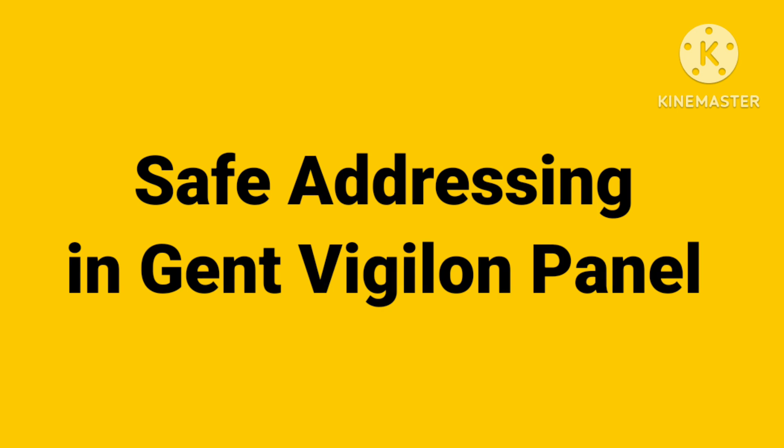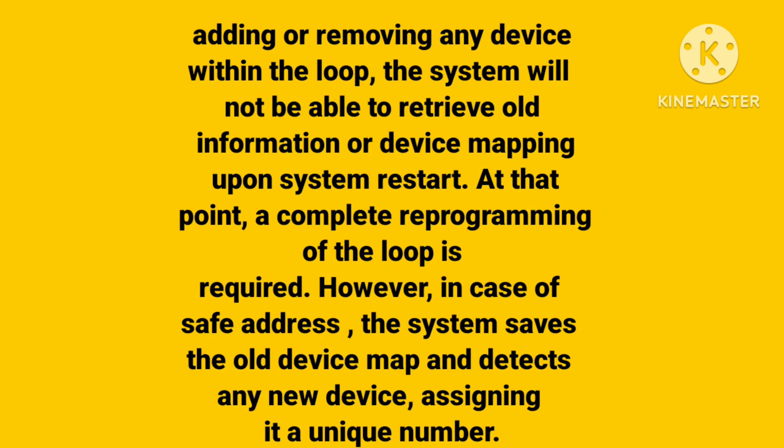In Gent Vigilon Panel, if we change our loop mapping or device locations — for example, if you remove any device from the loop and then reallocate the loop — the panel is not able to read the previous or old mapping. It will assign a new address. For example, if you remove device five from the loop, then in the new location, six will become five, and so on.